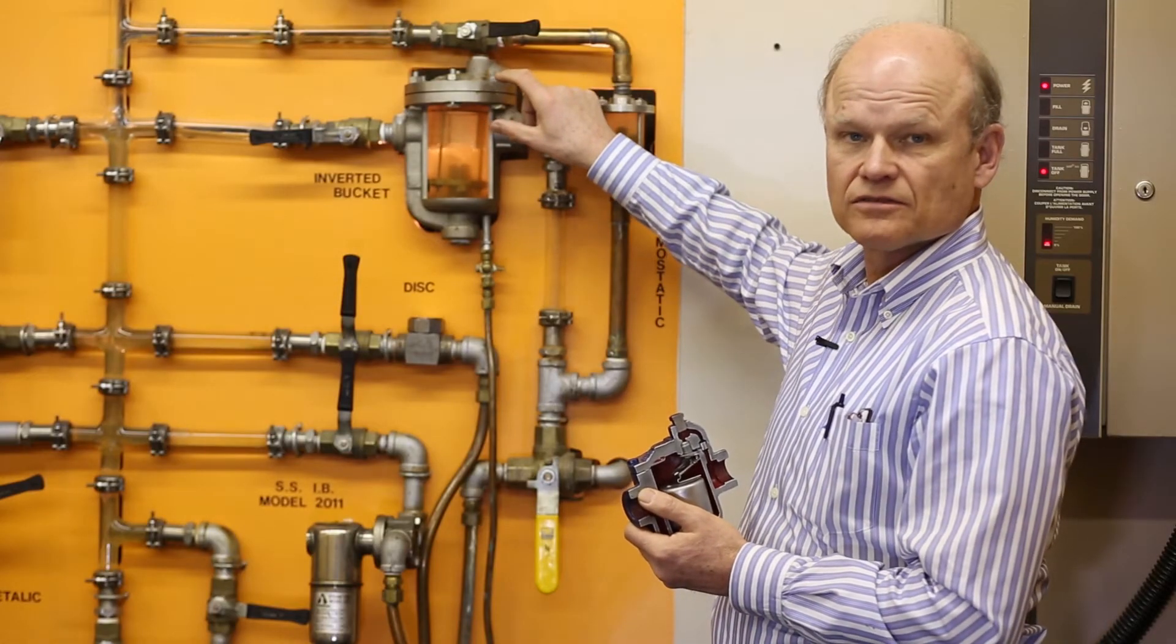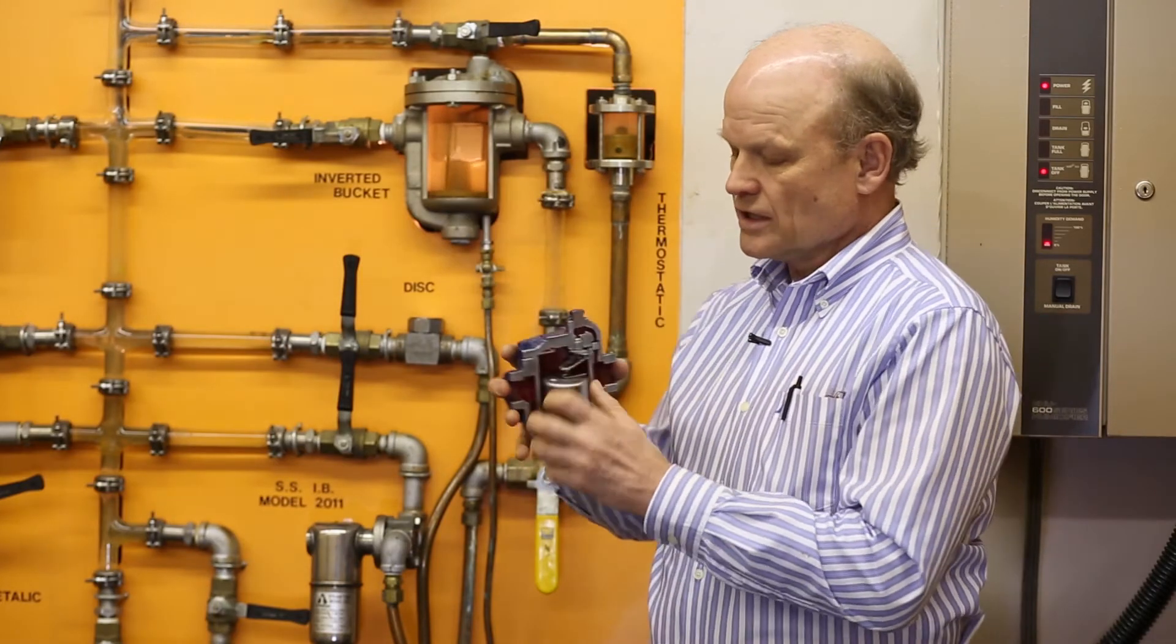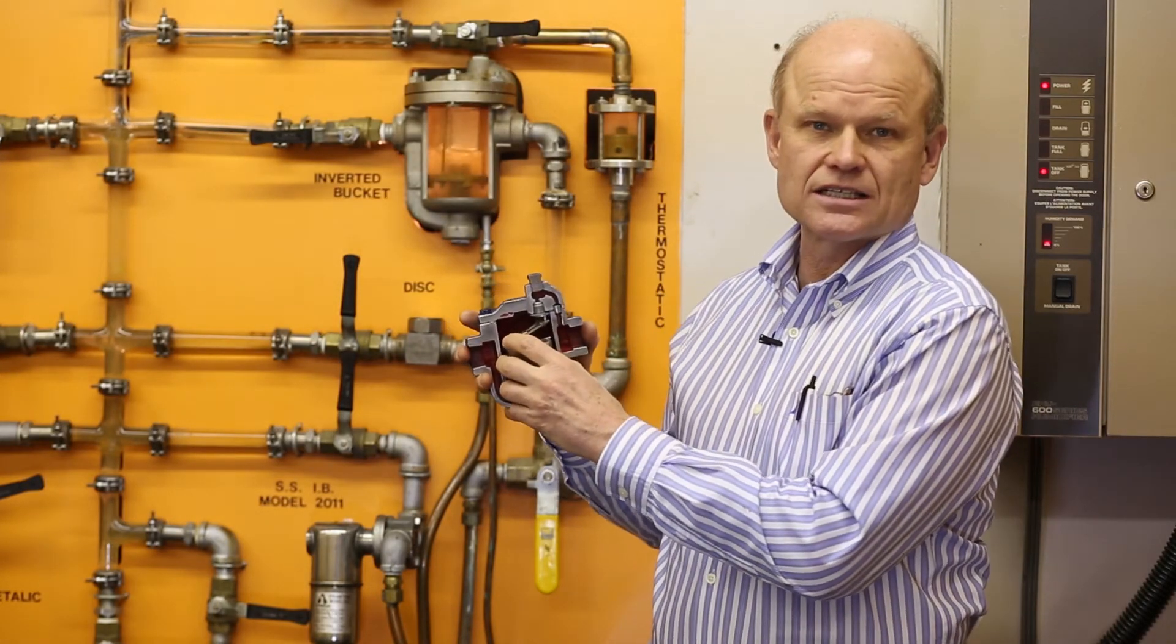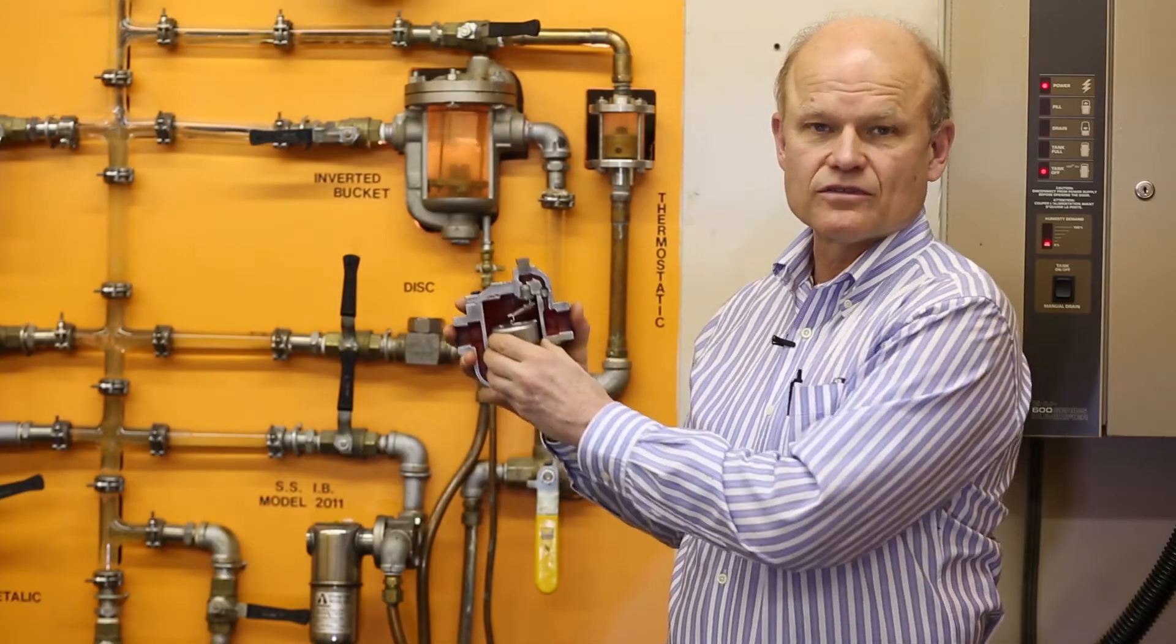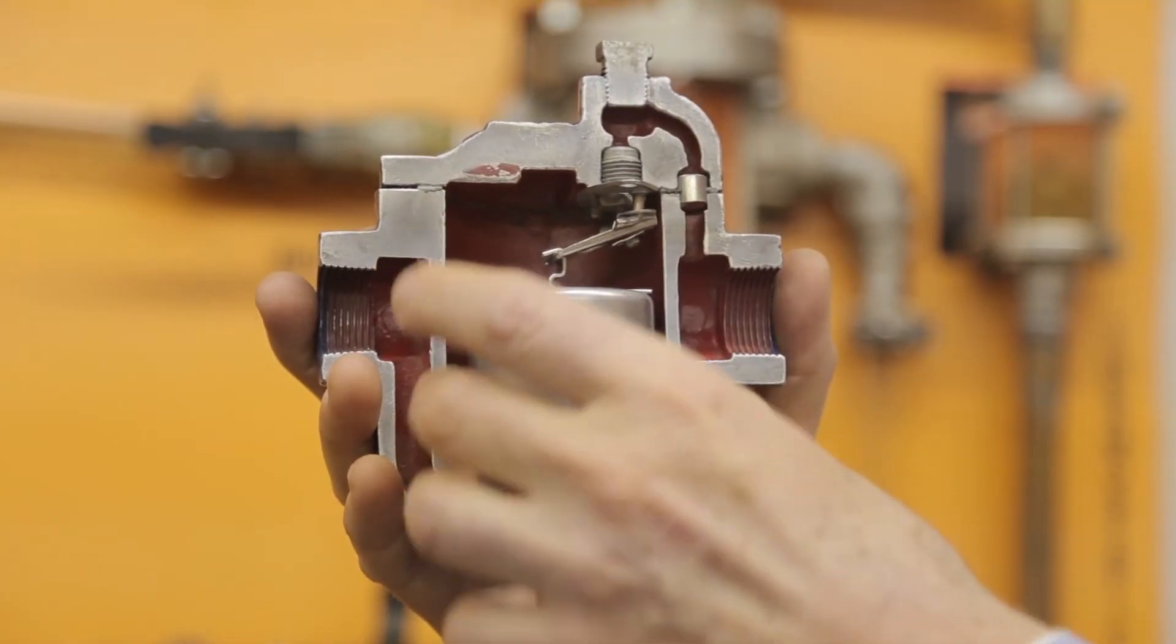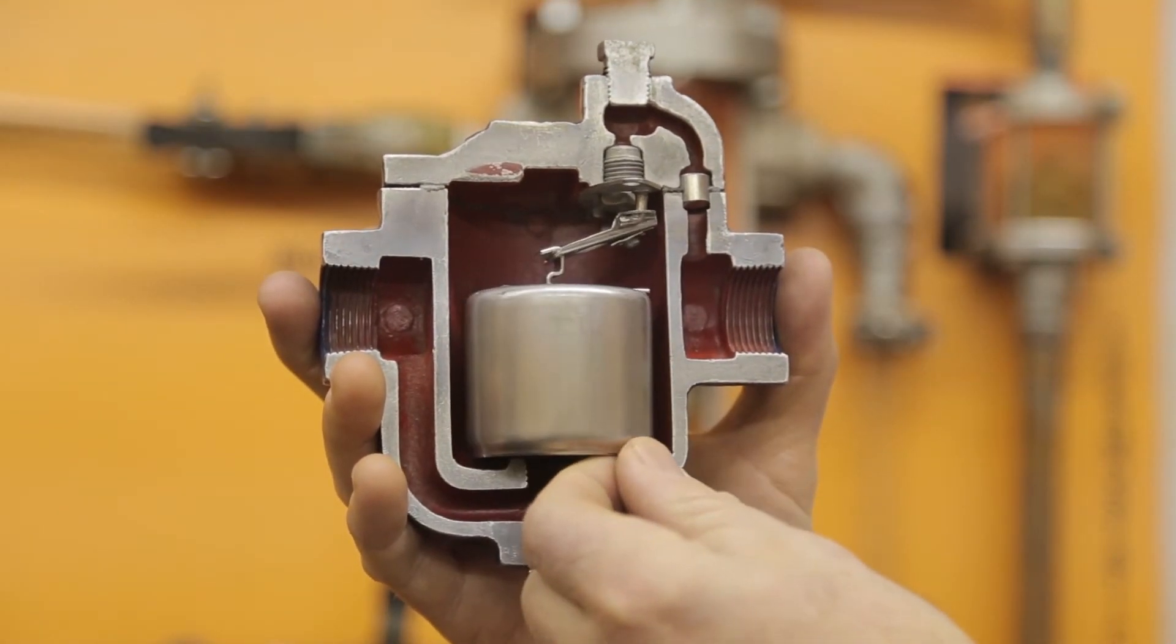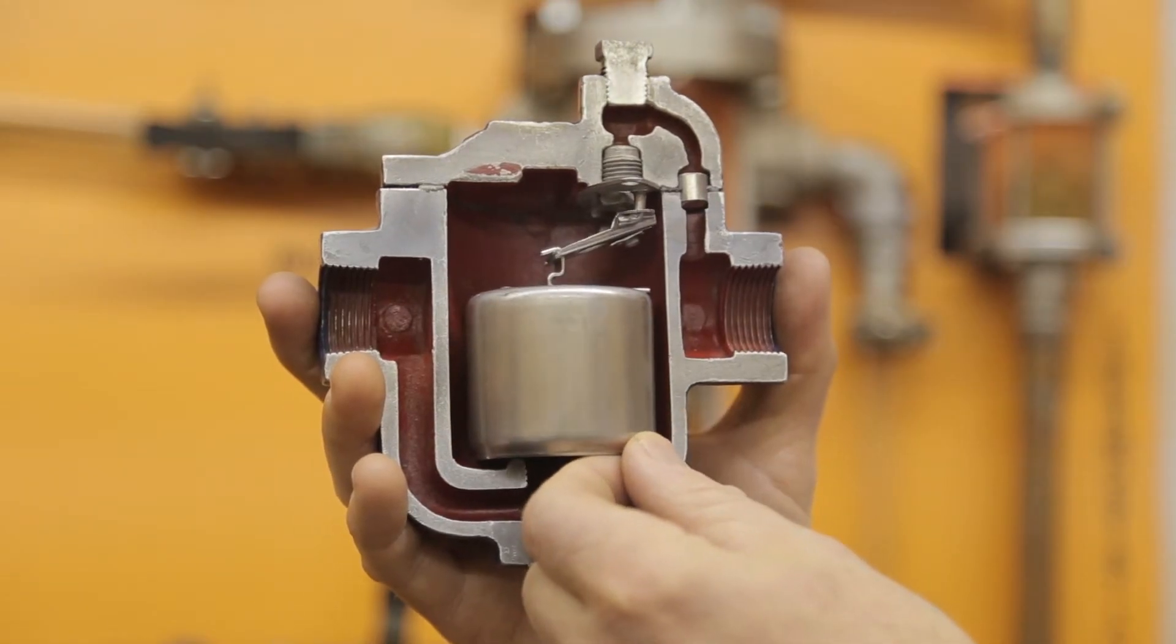There's also a small hole in the top of the bucket that allows for non-condensable gas and air to be vented out of this trap. So there are two components: the bucket removing the condensate and the bucket vent allowing for air and non-condensable gas to be vented.